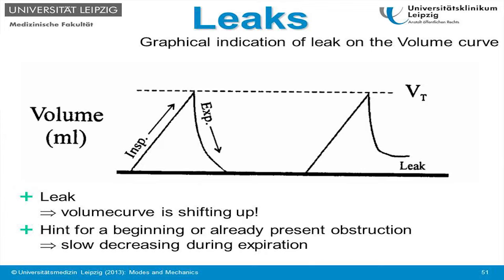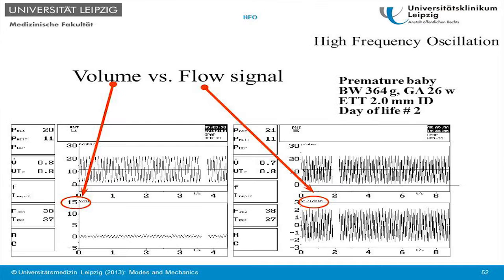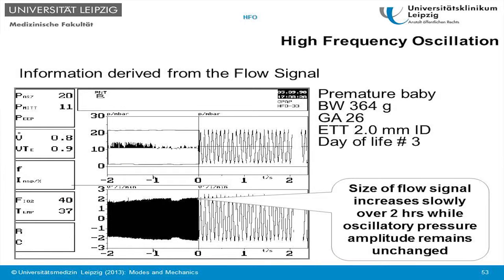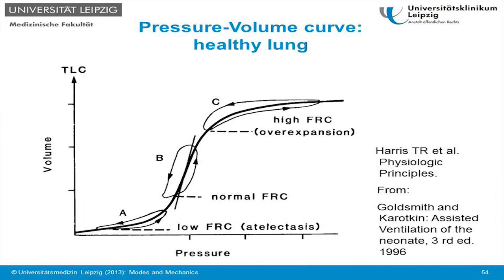The inspiration here, the expiration should go back to the same volume as before, but it doesn't, it stays up here. That means the volume curve is shifting up, and this is probably a leak around the endotracheal tube. In high frequency ventilation, you can see the beginning obstruction of the airway by observing the flow curve, and when the flow curve drops, then you probably have secretions and you need to suction the baby, and this information you get by using the flow sensor.